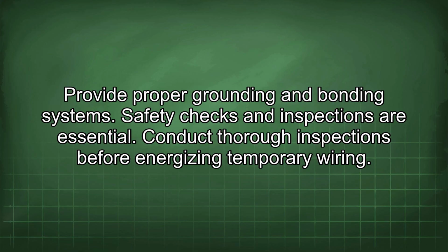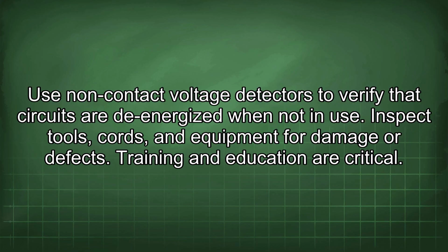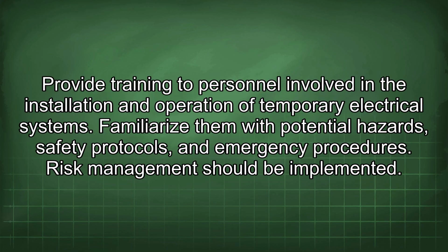Safety checks and inspections are essential. Conduct thorough inspections before energizing temporary wiring. Use non-contact voltage detectors to verify that circuits are de-energized when not in use. Inspect tools, cords, and equipment for damage or defects. Training and education are critical. Provide training to personnel involved in the installation and operation of temporary electrical systems. Familiarize them with potential hazards, safety protocols, and emergency procedures.